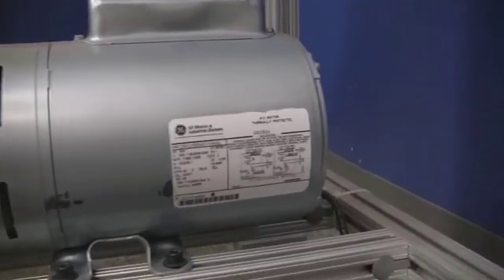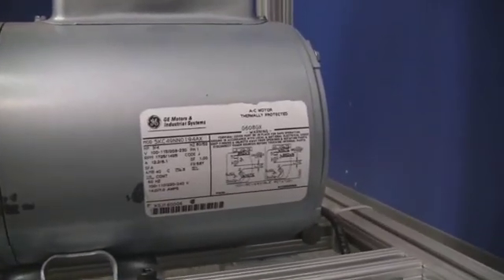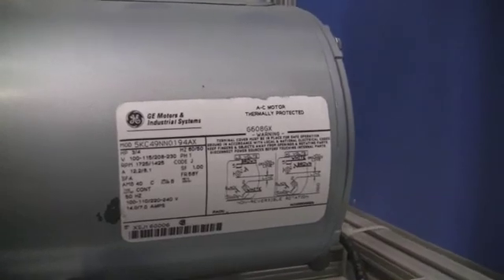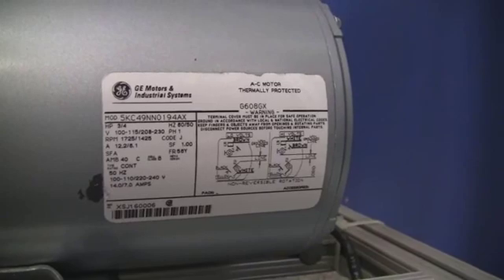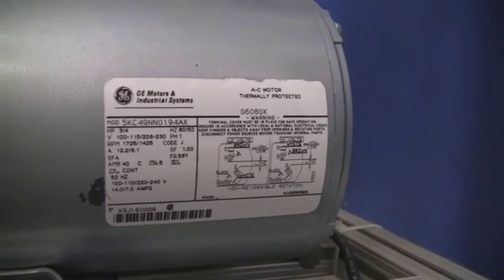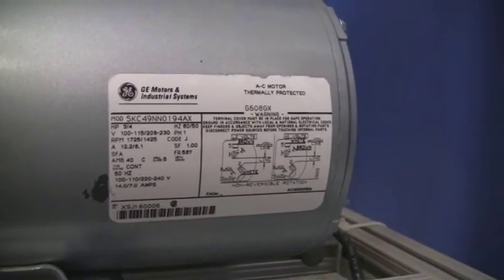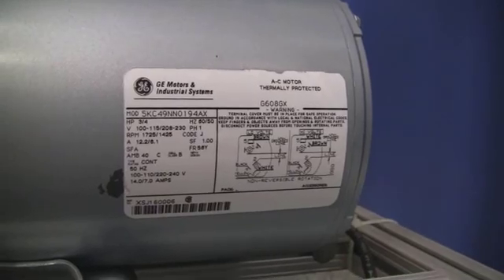It's very common to assume that the energy required to operate the mechanical pump is the same as the rating shown on the nameplate of the pump. But actually what's shown here is the horsepower output of the pump or the brake horsepower. The energy that's required to operate the pump isn't given but needs to be measured to be accurate.